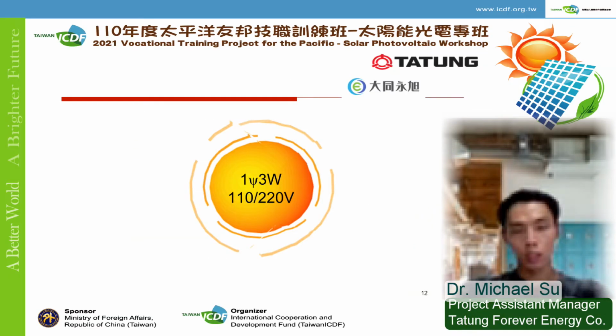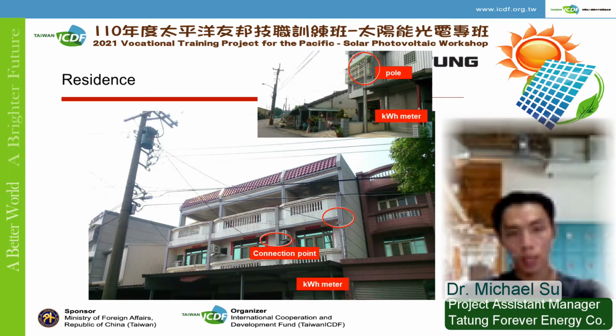Let's talk about a single-phase 3-wire system between 110 and 220 volts first. Here in the photo, you can see that there is a single transformer on top of the pole, usually for lower household electricity usage. And you can see that the area of the rooftop of the residential houses is pretty limited as well. So at most, we can put modules of lower than 20 kilowatts on it. Here I marked the demarcation points with red circles. Here we do that on the connection point on the wall, which is the entry point into the house for a lower voltage cable coming from the transformer.